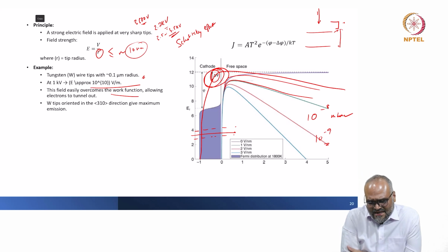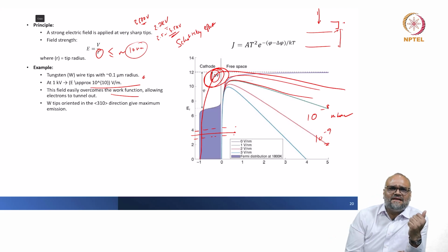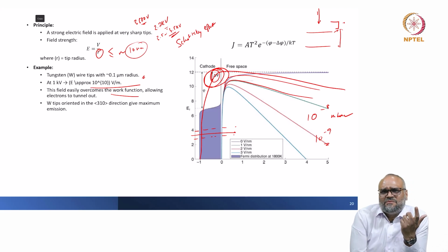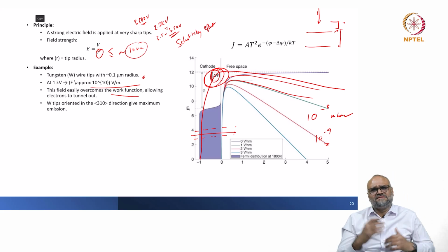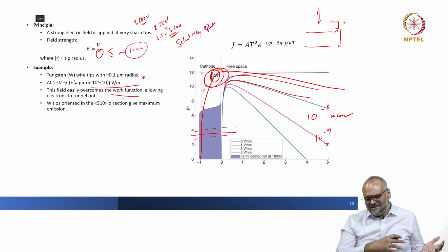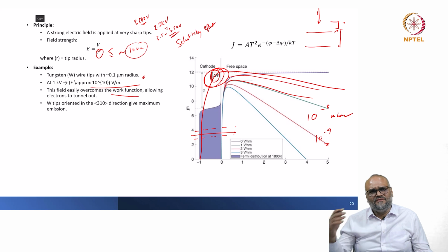So you would naturally have the formation of an oxide layer, and if you have an oxide layer on a conductive tungsten filament, bear in mind that the oxide can also have some kind of charging and flashing as well. So this will reduce the brightness or the flux that is coming out from a field emitter. So to overcome these, you would want to have a feedback loop.